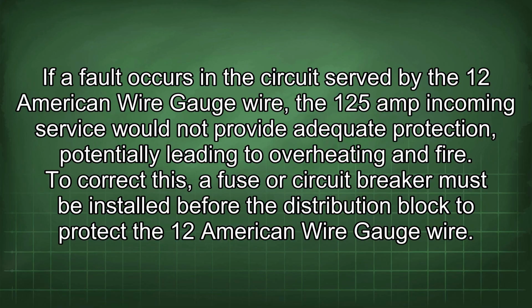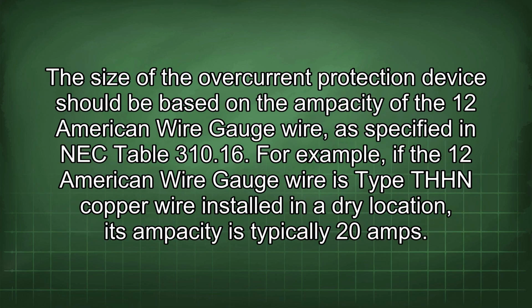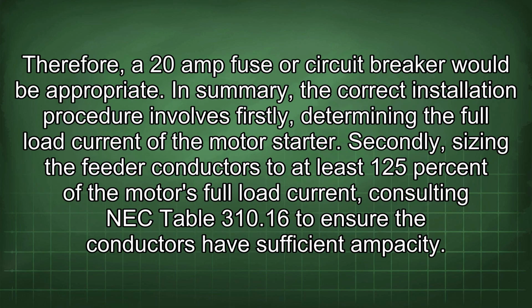To correct this, a fuse or a circuit breaker must be installed before the distribution block to protect the 12 American wire gauge wire. The size of the overcurrent protection device should be based on the ampacity of the 12 American wire gauge wire, as specified in NEC Table 310.16. For example, if the 12 American wire gauge wire is type THHN copper wire installed in a dry location, its ampacity is typically 20 amps. Therefore, a 20 amp fuse or circuit breaker would be appropriate.